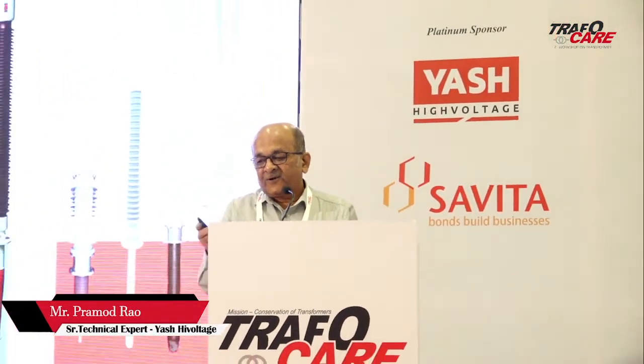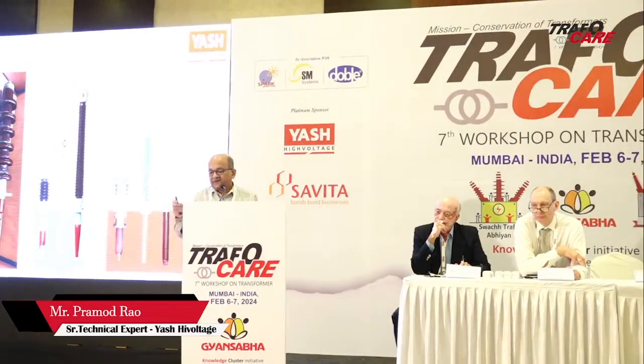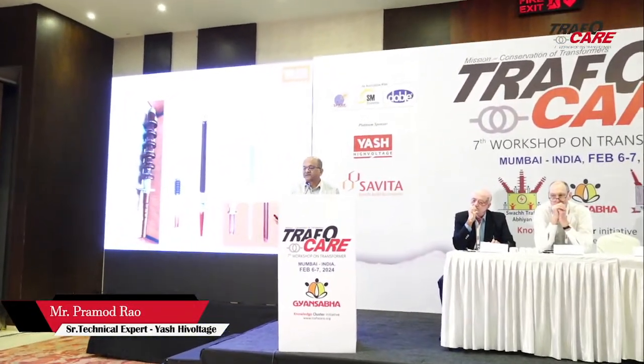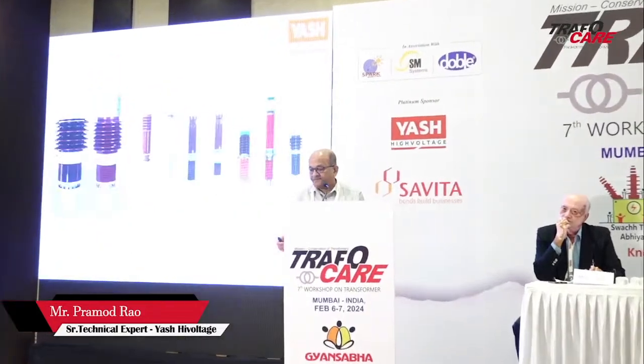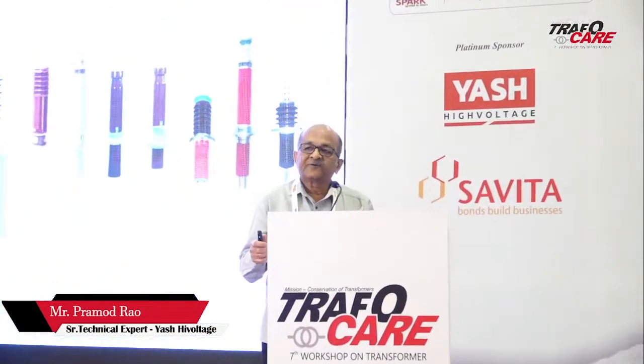Now let's look at various types of bushings. Air to oil type, typically less than 3150 amperes, and some special bushings for STATCOM applications at 6300 amps. On the leftmost side, what you see is the SRBP bushing, old technology. In the center, the three bushings you see are the OIP bushings. On the right side, you are seeing the RIP and RIS bushings. The white tail one is the RIS bushing.